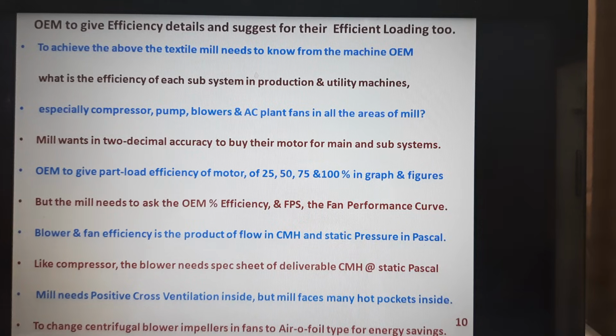And if it is a blower, the OEM has to give the fan performance curve, what is the CMH, what is the CFM deliverable by the blower at what static pressure. That is more critical here. The compressed air flow is talked of in terms of compressed air header pressure. The blower flow CFM is talked of in terms of static pressure only. At a given static pressure, at a given compressed air header pressure, at a given temperature and RH, how the AC plant is maintained, all these things are important here.